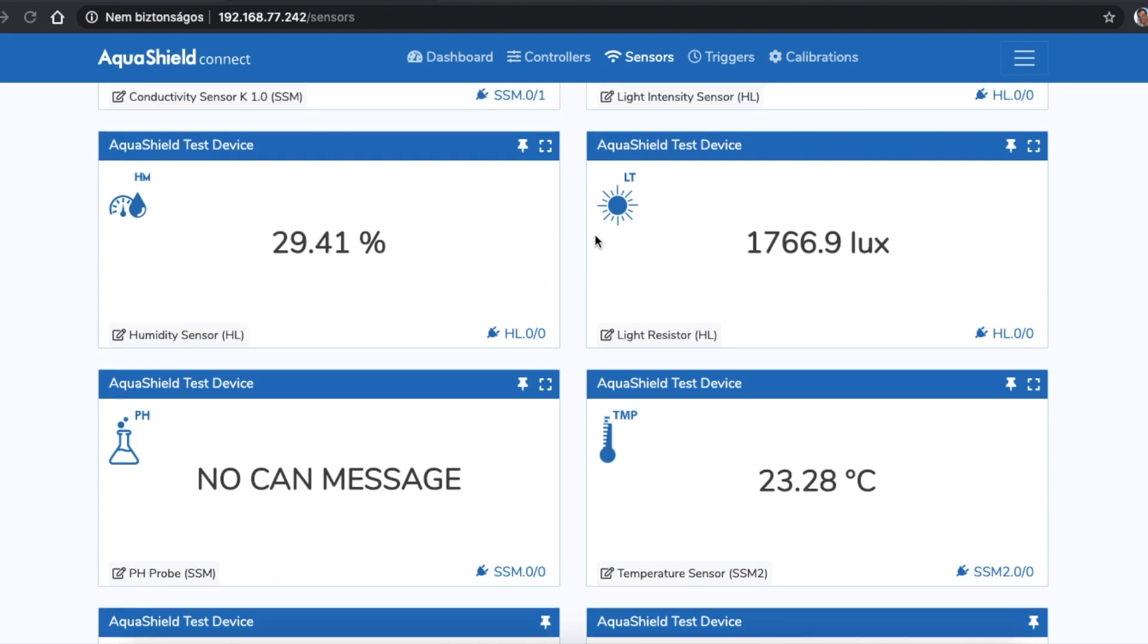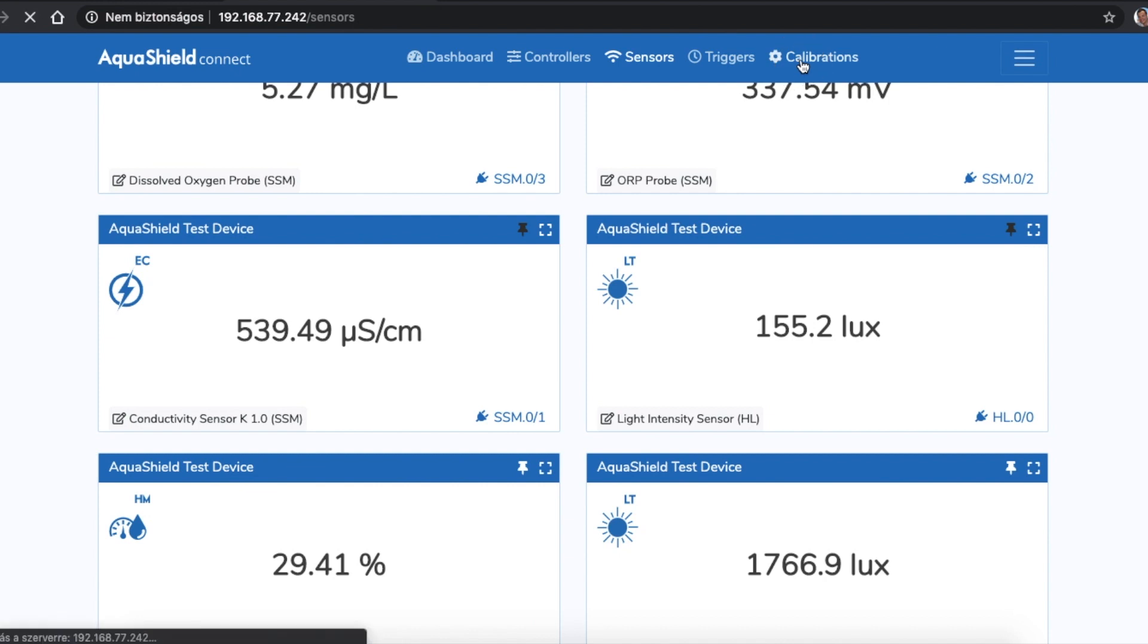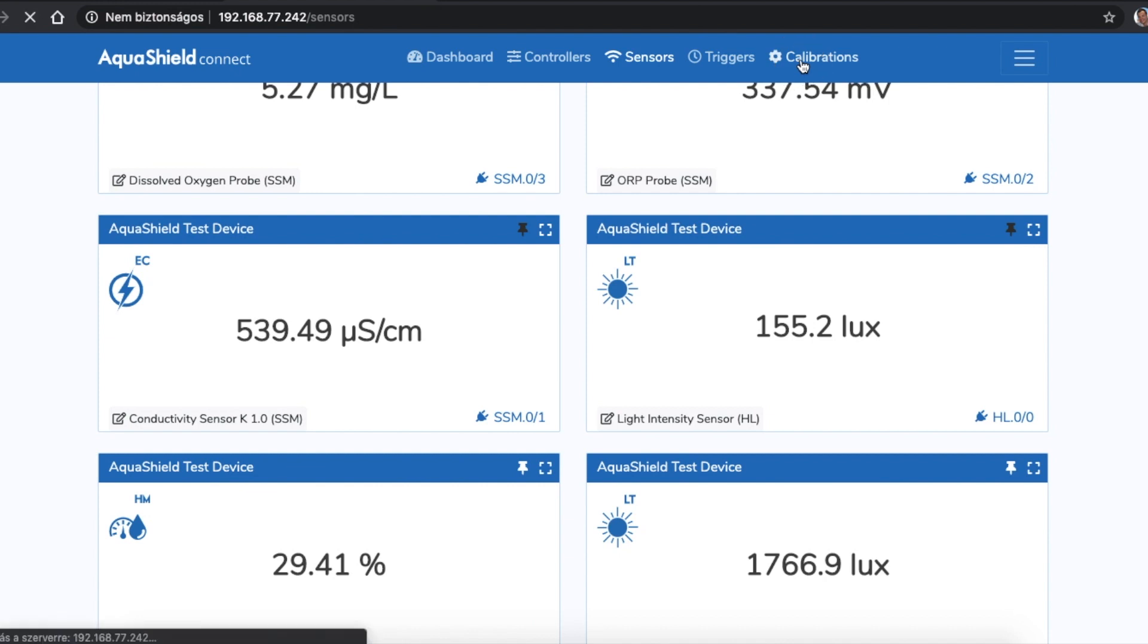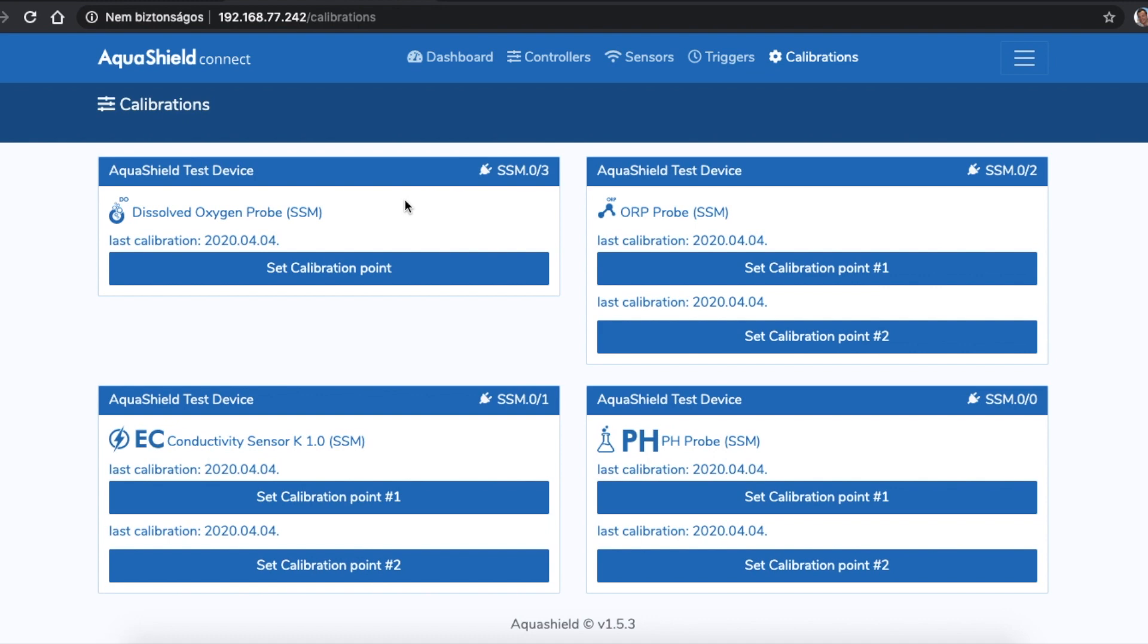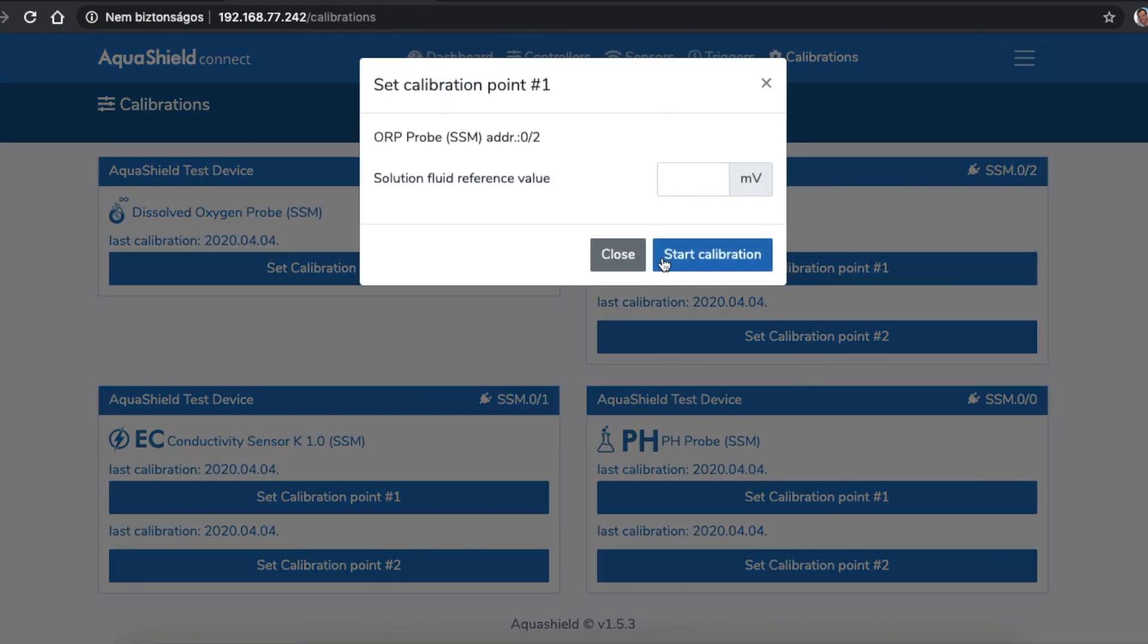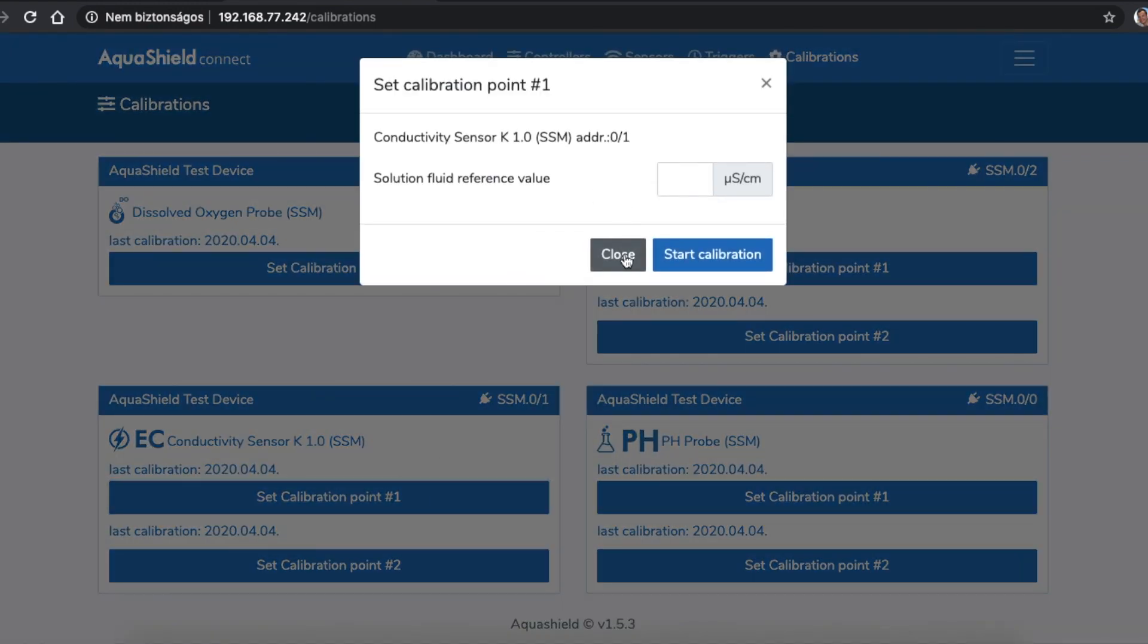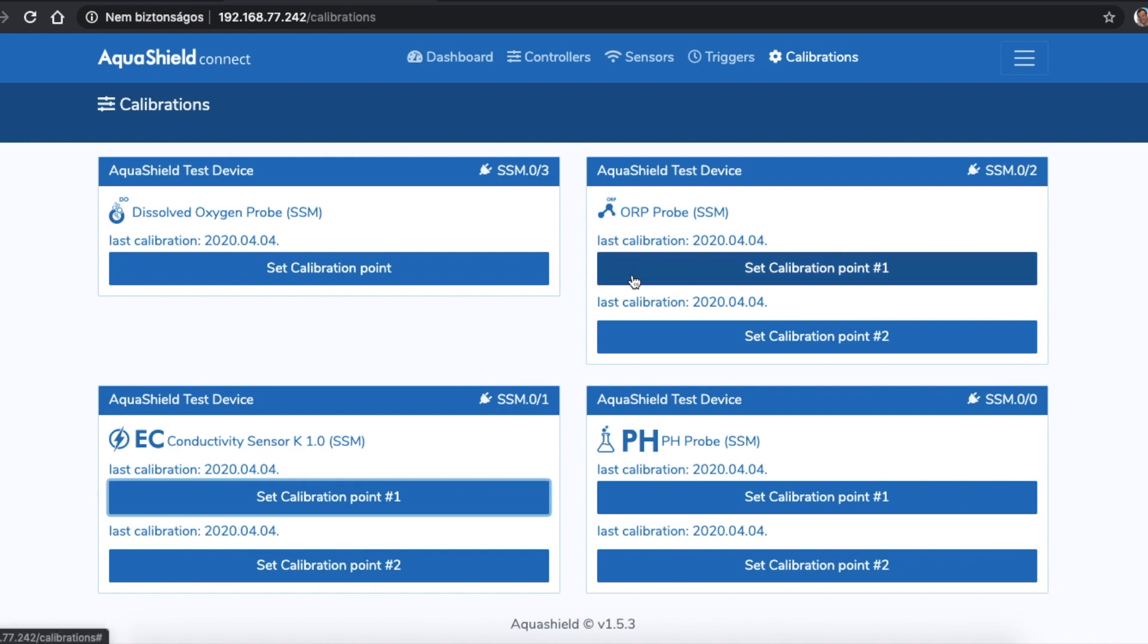For some of the probes, calibration is essential, as there are some minor differences even between pH sensors from the same manufacturing company. At this page, you can start 2-point calibrations for pH, EC, ORP and a 1-point calibration for dissolved oxygen. Of course, you will need calibration solution for every calibration point. We will show you the detailed calibration process in another video. If you use our recommended ATLAS scientific sensors, the values will be preset and will have a close to accurate to the factory settings.